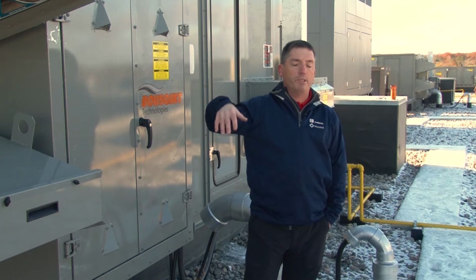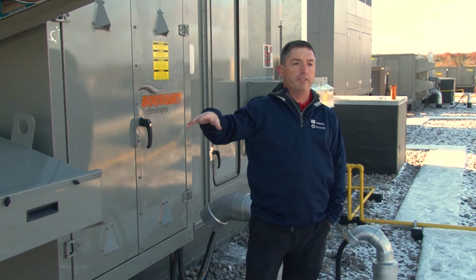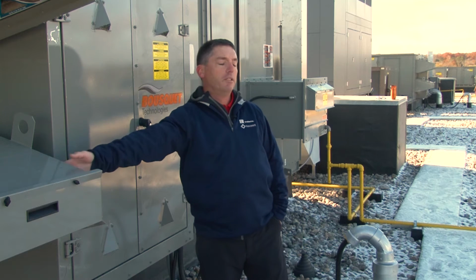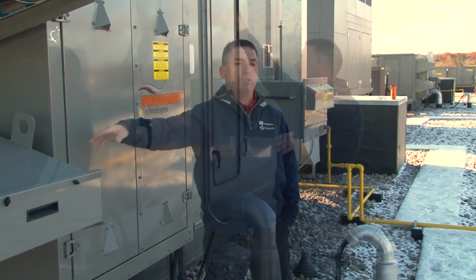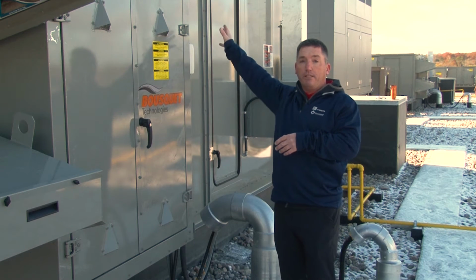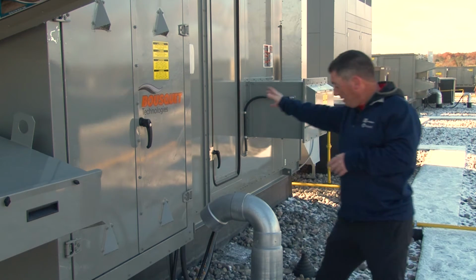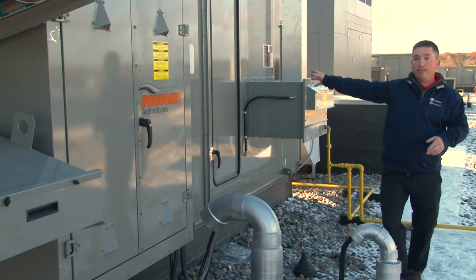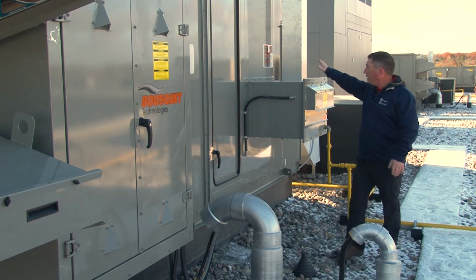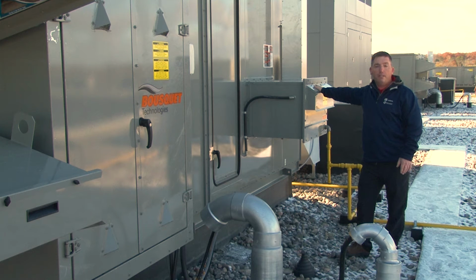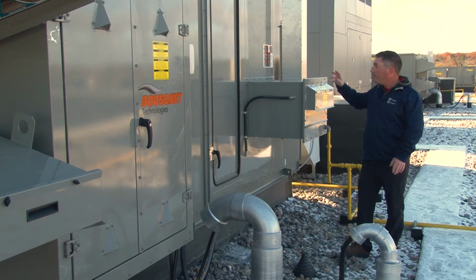The side that we're standing on now is the fresh air intake side, so outside air is going to be drawn in through these 2 hoods. The DX cooling coil is actually right here in this section. Supply blower is inside this door, which we'll cover, and then this section right here is the gas furnace.